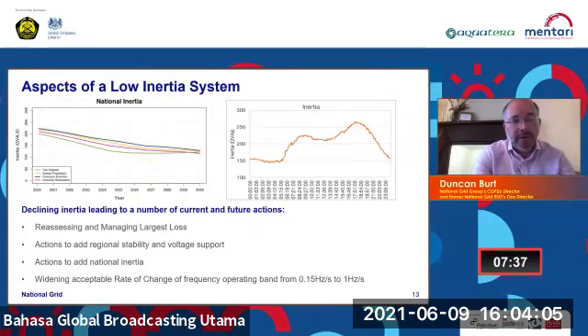So the first thing we do is we reassess and manage down the largest loss on the system. The largest loss is typically either one of the interconnectors, or two large units, or a single power station connected through a single circuit or a single breaker onto the rest of the system. And therefore an instantaneous loss of that breaker or of that unit would cause the largest single loss on the system and a collapse in frequency. We need to be able to operate the system and to secure that drop within our limits of plus or minus 1%. So if we reduce that largest loss, we reduce the inertial risk on the system.